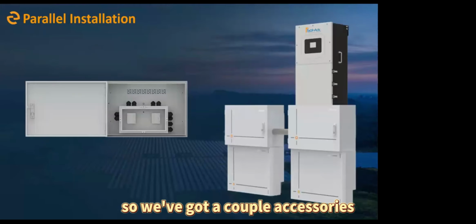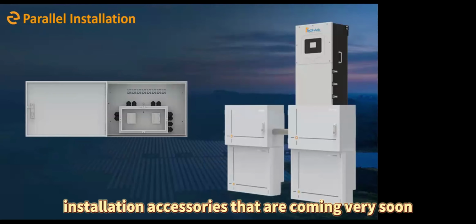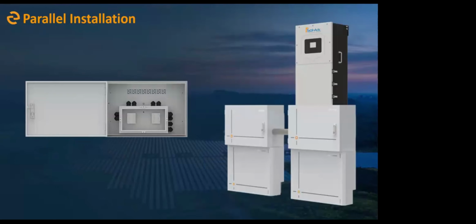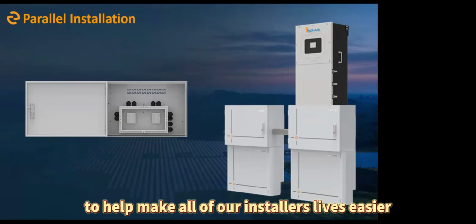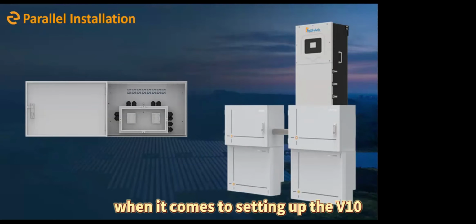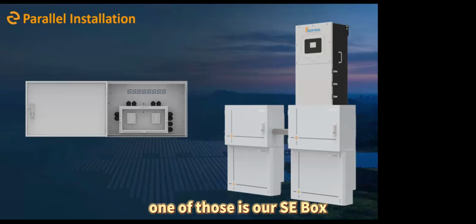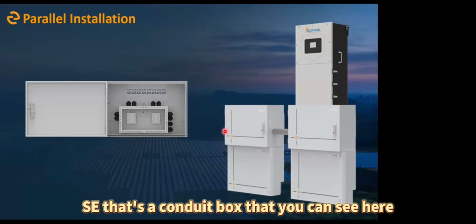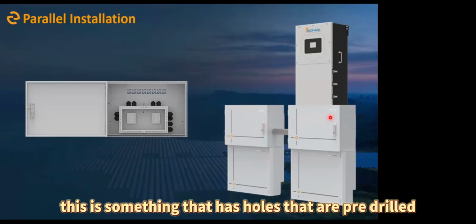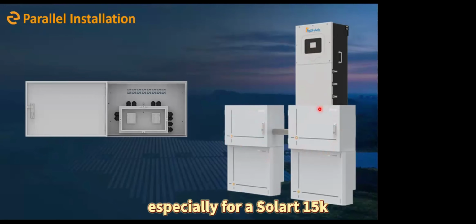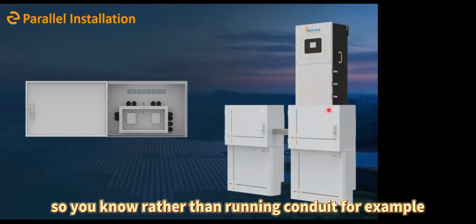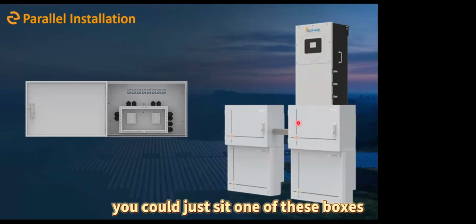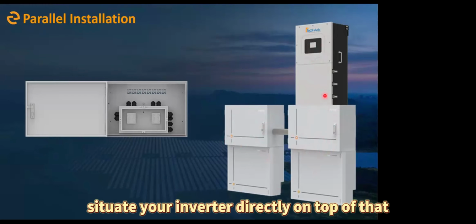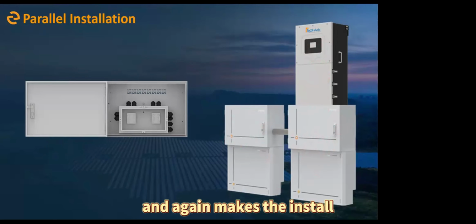So we've got a couple additional installation accessories that are coming very soon to help make all of our installers' lives easier when it comes to setting up the V10. One of those is our SE Box, a conduit box you can see here. This has holes that are pre-drilled, especially for a Solarc 15K. So rather than running conduit, you could just sit one of these boxes on top of the battery, situate your inverter directly on top of that, and that makes the install even easier.